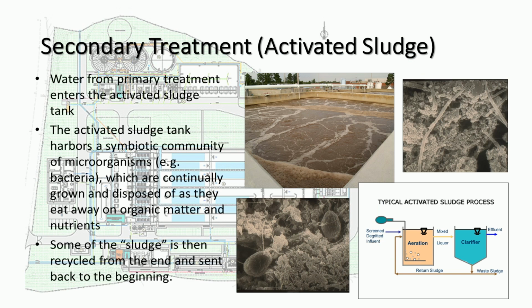One particular biological method used extensively in wastewater treatment is activated sludge. Activated sludge treatment utilizes a series of tanks where microorganisms are grown under specific conditions. The nutrient-rich wastewater stream supplies the microorganisms in these tanks with food to grow and multiply continuously.